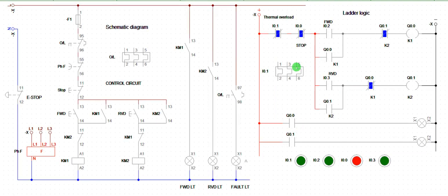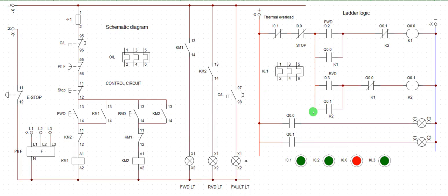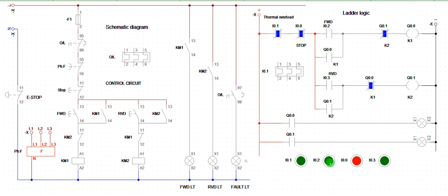Let's try once more. I want to find out something. I put on this logic. It's running. Oh, yeah, it's working. I'll create the fault from here. All right, so it's better. Okay, now when this logic is on, when the forward operation is working, and I have a fault tripping from here, so let me activate this. So the system shut down.